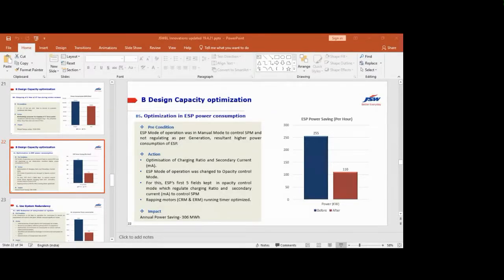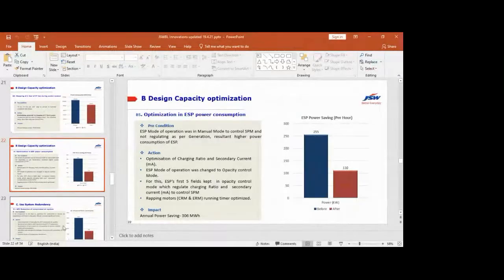To meet the environmental norms, we did this exercise so that we can get the SPM level as well as the APC reduction. For this ESP, the first 5 fields were kept in the opacity control mode, which regulates the charging ratio as well as the secondary current to control the SPM, and the rapping time of the motors was also optimized. The annual power saving is 306 megawatt hour.